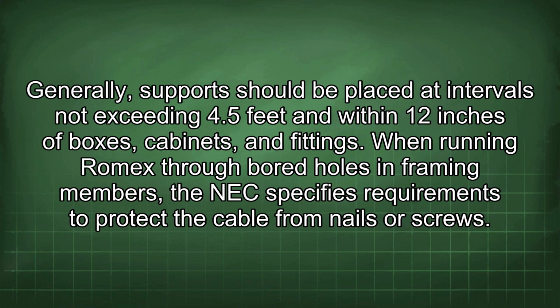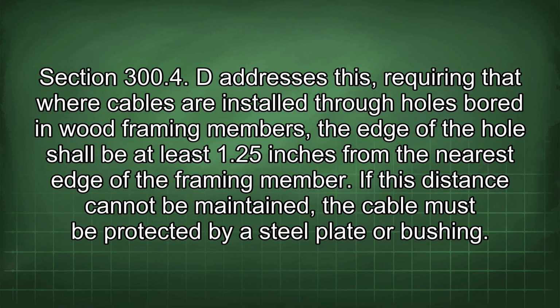When running Romex through bored holes in framing members, the NEC specifies requirements to protect the cable from nails or screws. Section 300.4(D) addresses this, requiring that where cables are installed through holes bored in wood framing members, the edge of the hole shall be at least 1.25 inches from the nearest edge of the framing member.